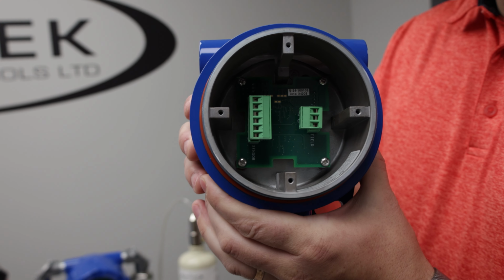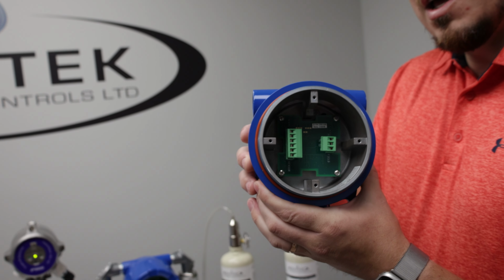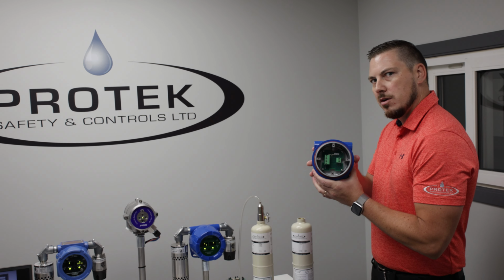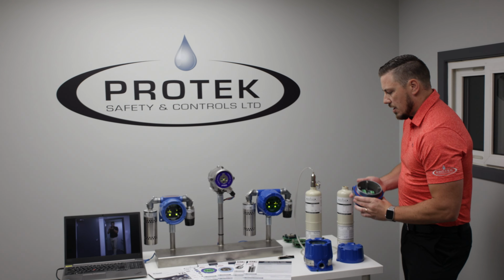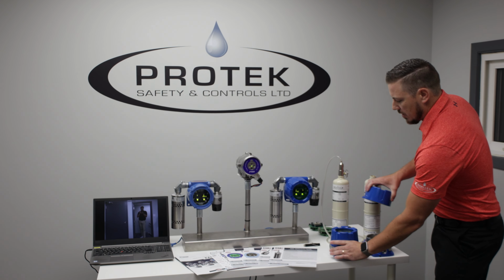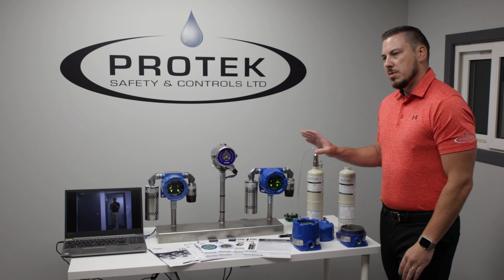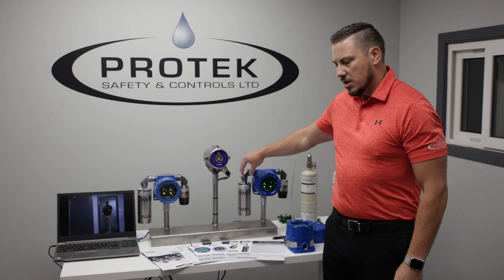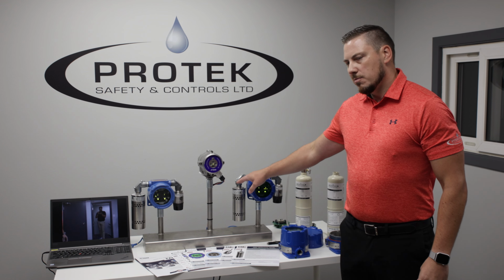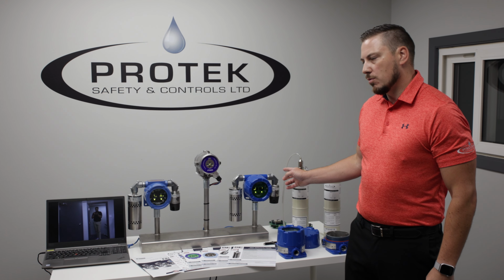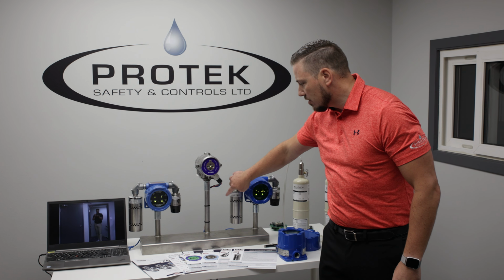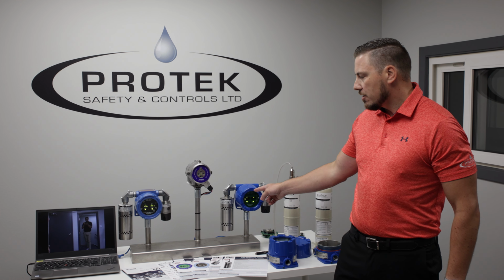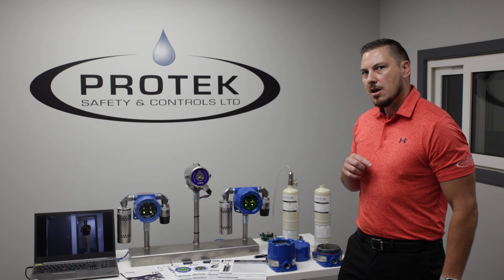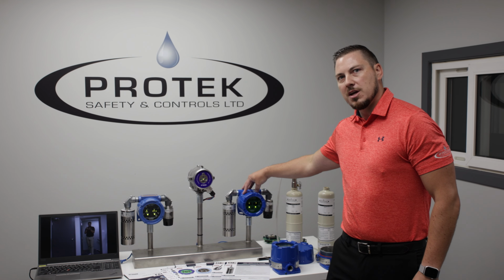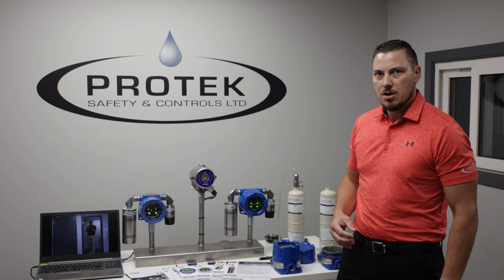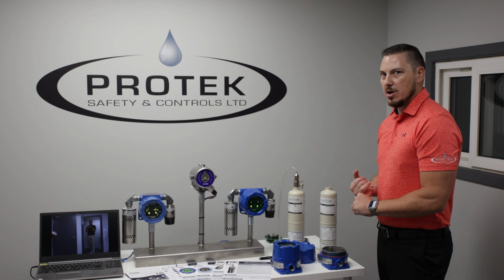Inside you'll see that we've got a little PCB that embeds the data on the power wire using our proprietary technology that communicates with our universal display module and populates it. One of the big technical benefits with our sensor electronics gas detection is that our transmitter is built into the sensor head itself. So we're pushing a 4 to 20 signal from the sensor head right on back through the display to your PLC. All we're doing is populating the display here, allowing for remote communication and accessibility for remote calibrations.